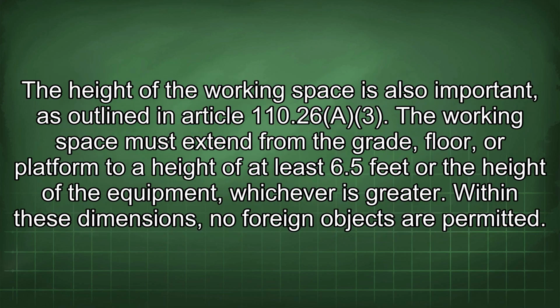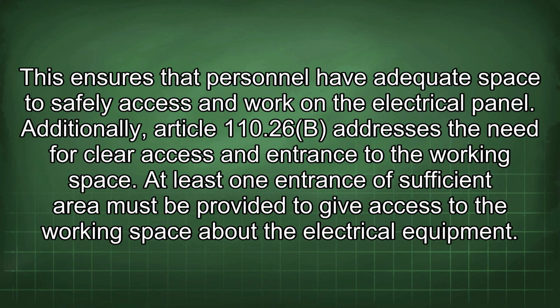The height of the working space is also important, as outlined in Article 110.26(A)(3). The working space must extend from the grade, floor, or platform to a height of at least 6.5 feet or the height of the equipment, whichever is greater. Within these dimensions, no foreign objects are permitted. This ensures that personnel have adequate space to safely access and work on the electrical panel.